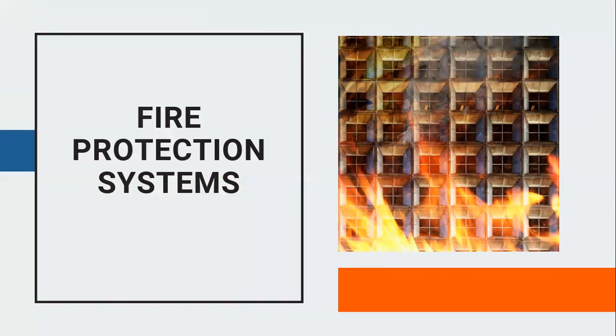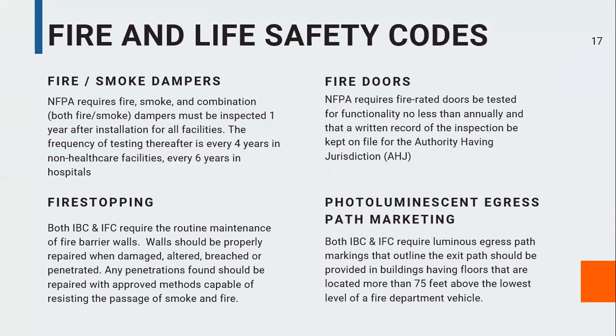So let's talk about NFPA and those codes that are so important and even more important as we shelter in place in some facilities and areas as we maintain code. So fire and life safety codes have not been amended or repealed or suspended. So your fire and smoke dampers are very important systems that the NFPA requires be inspected. Both fire and smoke dampers and combination dampers must be inspected the first year after installation for all facilities. The frequency of testing thereafter is 4 years for non-healthcare facilities and every 6 years after that for hospitals. So this means all buildings where these devices are in place.